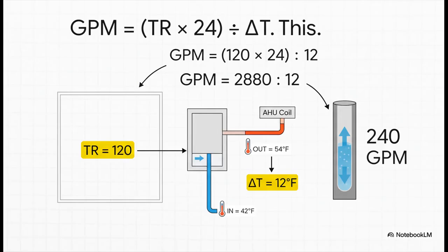Okay, next up, we need to know how much water the pump needs to move. That's the flow rate. For that, we use the standard formula here. We just plug in the cooling load for that one zone in TR and the system's design temperature difference, the delta T, and boom, that gives us our gallons per minute. Now we know exactly which pump to order.